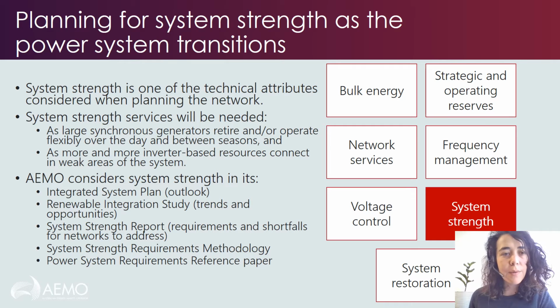With system strength, we are looking at the ability of the system to provide sufficient fault level or sufficient resilience to changes in the voltage waveform, and that traditionally has been provided by injection of fault current from synchronous generators, but there are a range of different ways that we're looking at planning for that system strength and resilience as the system changes. A lot of our thinking is captured in some documents that are already published.